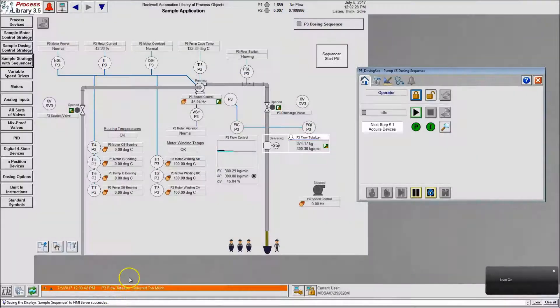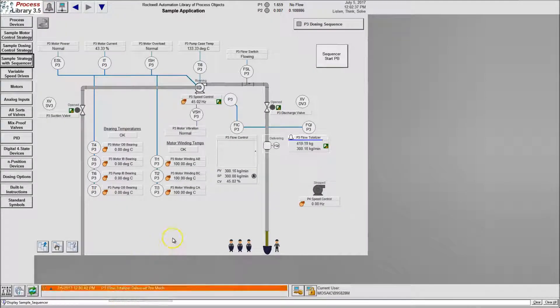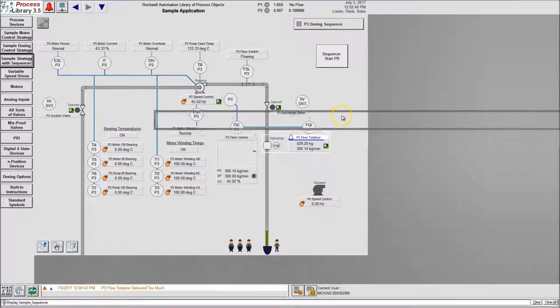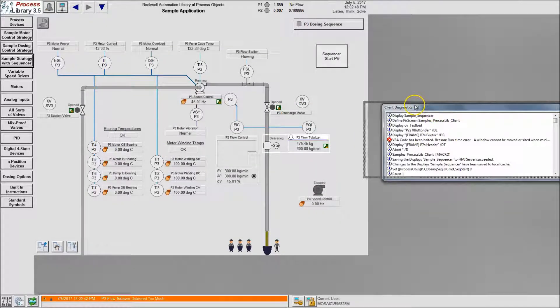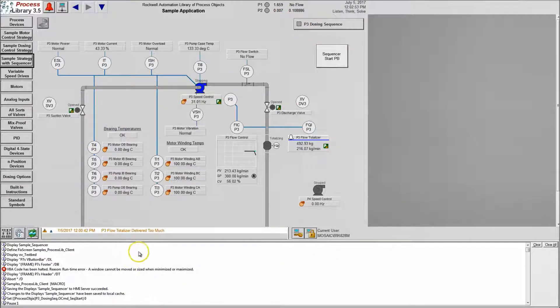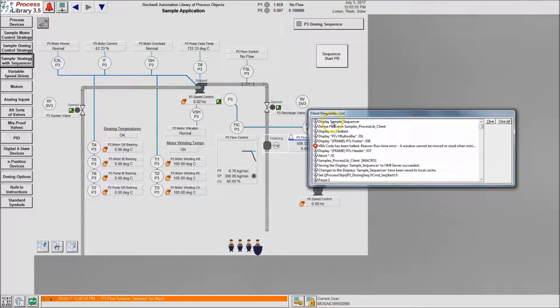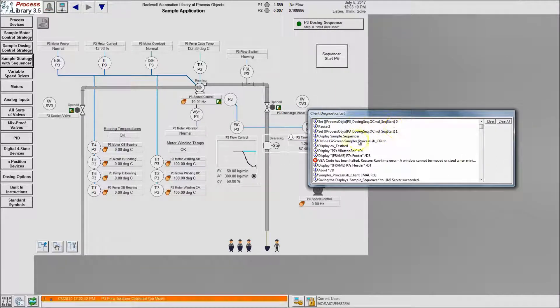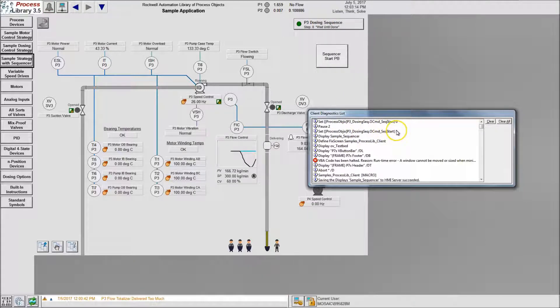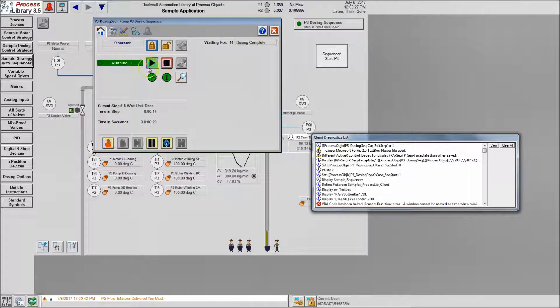Let's change that to two seconds, save, refresh, and see it in the bottom diagnostic area. When I push this button you'll see the tags come in - it set a one, waited two seconds, and then set a zero. Then it started the sequence right here, then paused, then set a zero. So the button is essentially not pressed anymore - the bit has been properly reset.